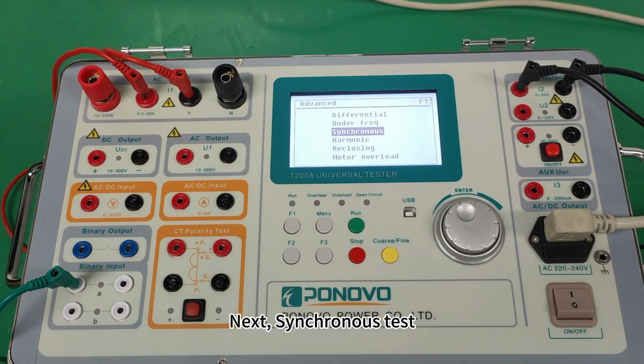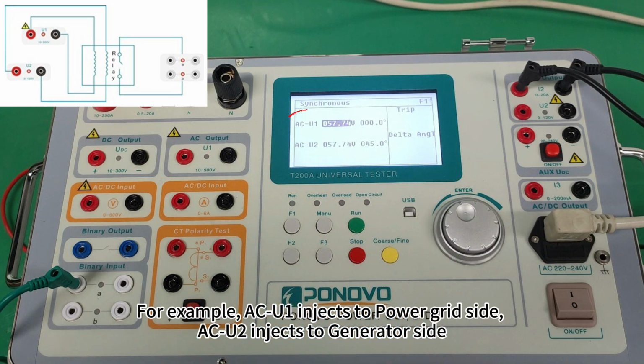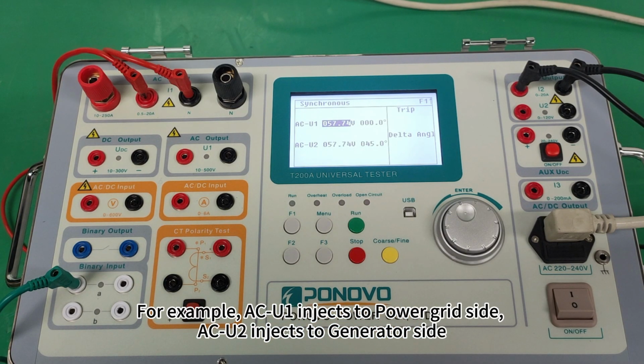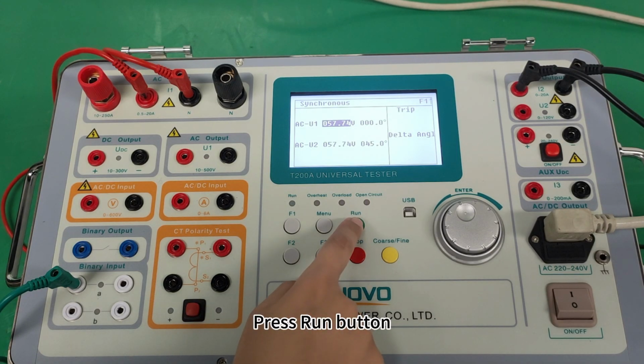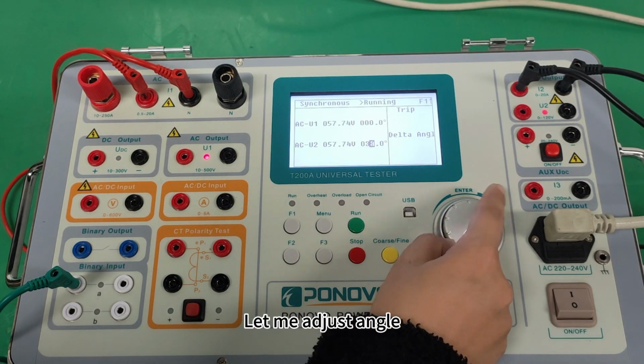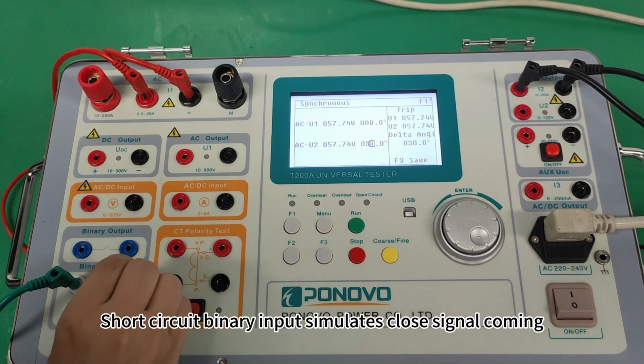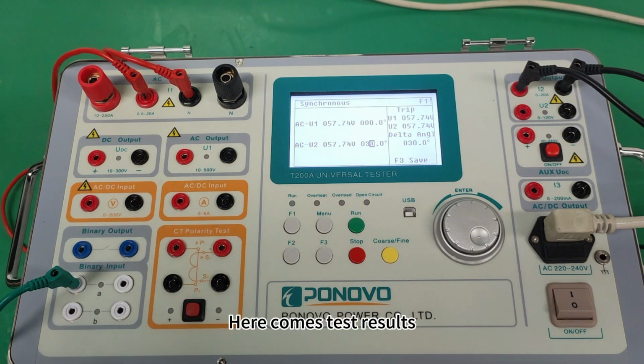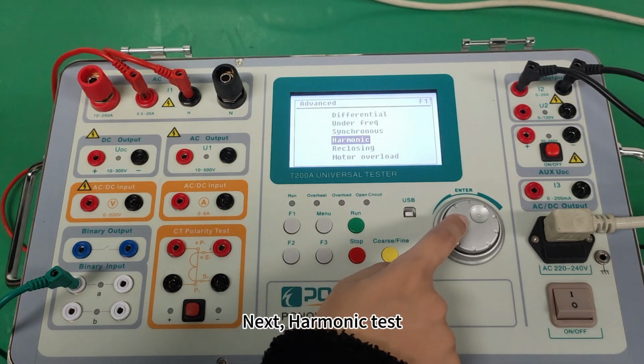Next, synchronous test. For example, ACU1 injects to power grid side, ACU2 injects to generator side. Press Run button. Let me adjust angle. Short circuit binary input simulates close signal coming. Here come test results.